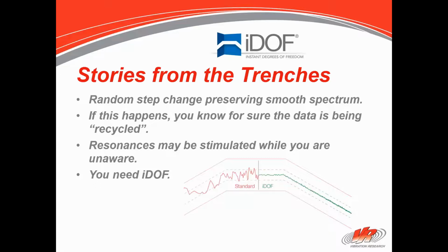And then we tell everyone to go do that, and we look at the results coming out of the voting machine. And if the results coming out of the voting machine don't match what we put into it, we know that something different is going on. And that's the technique that iDOF uses. We know exactly what drive is going to the shaker, with the phases and everything. If they don't match, then we know there's a problem or an issue. And we can predict with almost 100% certainty exactly what the system is going to look like, even though you don't have 5 minutes of data, what it looks like right now. So that was a cool story from the trenches and what's actually happening.